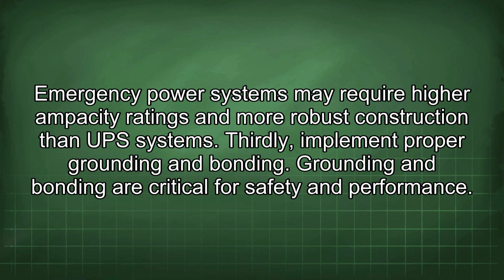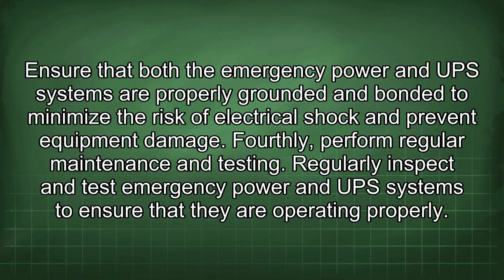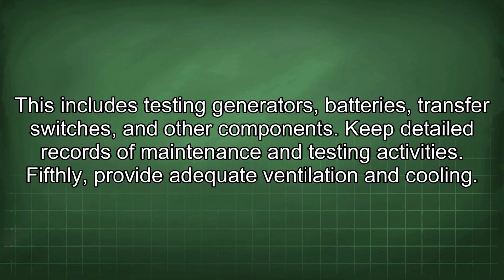Thirdly, implement proper grounding and bonding. Grounding and bonding are critical for safety and performance. Ensure that both the emergency power and UPS systems are properly grounded and bonded to minimize the risk of electrical shock and prevent equipment damage. Fourthly, perform regular maintenance and testing. Regularly inspect and test emergency power and UPS systems to ensure that they are operating properly. This includes testing generators, batteries, transfer switches, and other components. Keep detailed records of maintenance and testing activities.